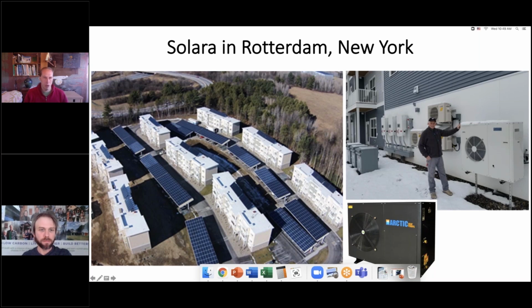So CO2 is one of many refrigerants, but it is at the very lowest end. CO2 has a global warming potential of 1. That's important. Refrigerants can be very bad chemicals. Propane's got a global warming potential of 3. That's awesome. But we don't get much propane in the U.S. because of UL listings and fire risks and such.